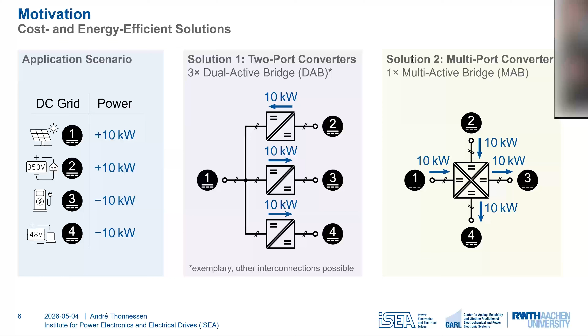But if we look at the power transfer from port 2 to port 3, for example, we see this power is transferred through 2 of the two-port converters, thus involving 2 times the losses. For the multi-port converter-based solution, there is only 1 energy conversion stage in between. Thus, we can reduce the costs, reduce the losses, and increase the efficiency.